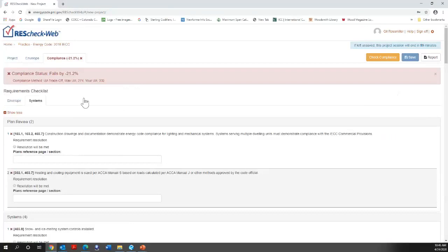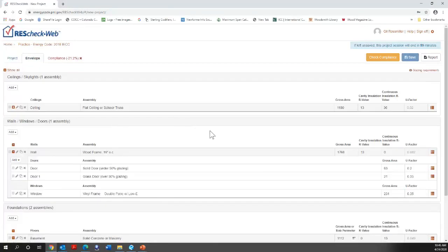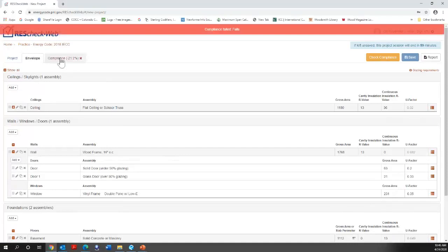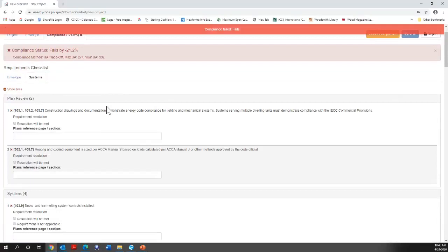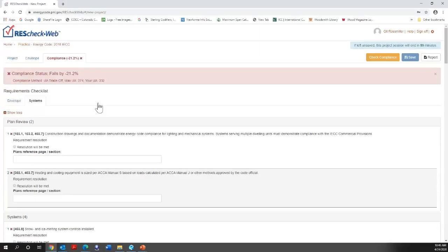Yeah, there's a checklist. So we'll just use this because, even though it fails, we're not going to have time to go through. But that's a great question. I don't care if they're finishing it or not. Is it inside or outside of the thermal envelope? That could be a completely unfinished basement, the drape, and everything. That's the key. And so if you've got a builder that says, well, but we're not finishing it, well, yeah, so is it inside or outside your building thermal envelope? Tell me that. If it's not, then you're insulating the entire floor, okay? Putting your air barrier on your floor.